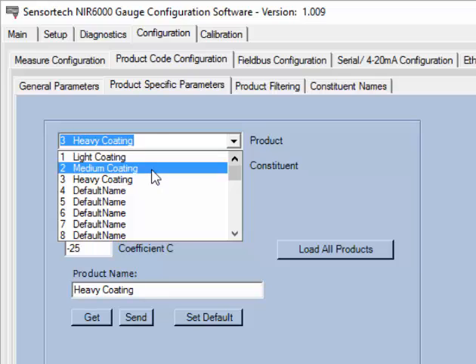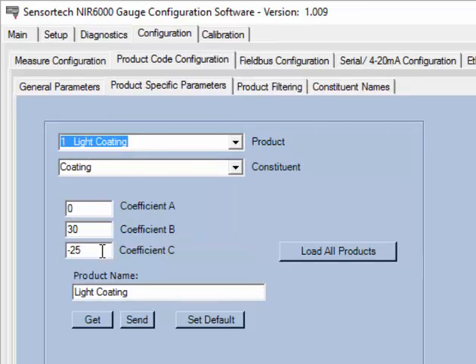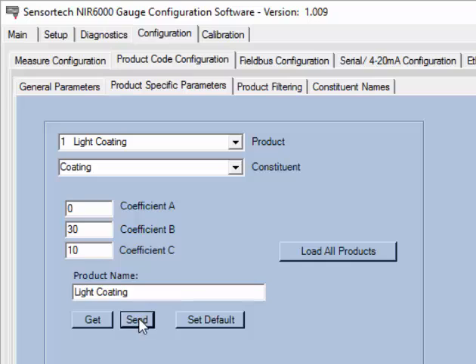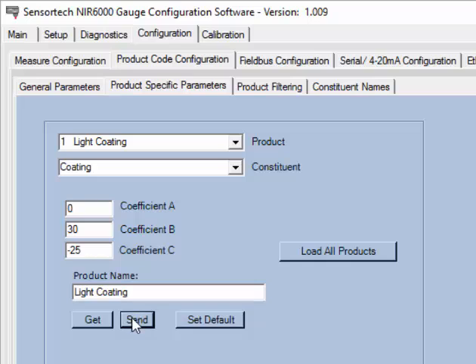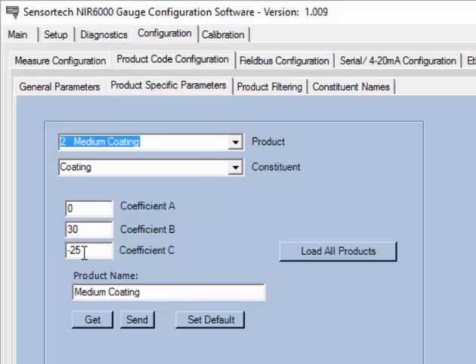Calibrating each of the product or calibration codes using both B and C coefficients is done from the Calibration tab, but this is out of the scope of this demonstration. Calibration is a simple process and the relationship between the analyzer's measurement and the constituent being measured is linear. Thus, the calibration is essentially the equation of a line with Coefficient B being the slope and Coefficient C being the y-intercept.